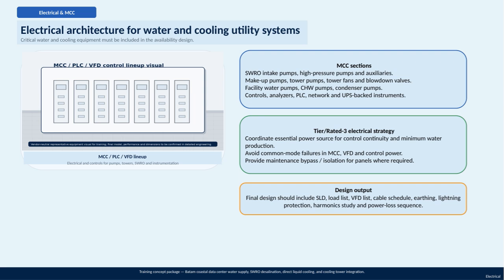On the electrical side, we look at the MCC, PLC, and VFD lineup. These components play a vital role in the electrical control, pumps, cooling towers, SWRO units, and various instrumentation throughout the facility. The MCC sections cover several critical equipment groups: SWRO intake and high-pressure pumps, makeup and tower pumps, tower fan, and blowdown valves, along with facility water, chilled water, and condenser pumps. All these are controlled and monitored via analyzers, PLCs, network systems, and UPS-backed instruments to ensure continuous operation.